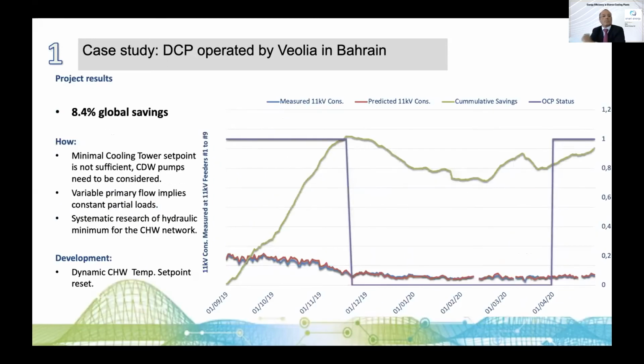So the results are very good. We're very satisfied with the result. We've achieved 8.4% savings based on the overall plant consumption. This was a proof of concept. This was our first reference in the Gulf, so we decided to go through an on-off validation. The OCP solution was on for 3 months, between the 1st of September and the 1st of December, which was interesting in terms of representation because it covers a little bit of summer and the mid-season, which is usually where it's difficult to find the optimum set point due to significant changes in the weather occurring. And what you can see on the green curve is the cumulative savings over the period, and you can see that as soon as the solution switched off, the savings stop.